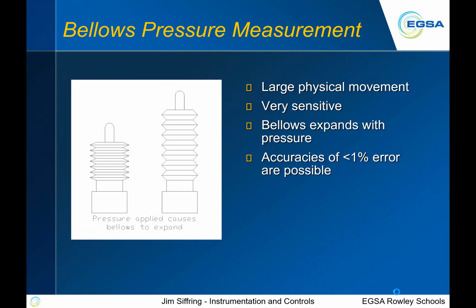Now look at bellows pressure. I keep this graphic in here because to me it's counterintuitive. You'll see the two devices within the graphic there, and basically it's a bellows. You screw that into some area that you want to measure the pressure on. For me, it seems that if you would increase pressure, the device would get shorter, like on the left. That's actually the natural state. If you apply pressure to it, it actually gets longer. To me, that's counterintuitive. That's the reason I put the graphic in there, just to be aware that what's happening on this device may not be what you think is happening. So the bellows expands as you add pressure. Those types of devices, I don't see a lot of them, but they can be pretty accurate.